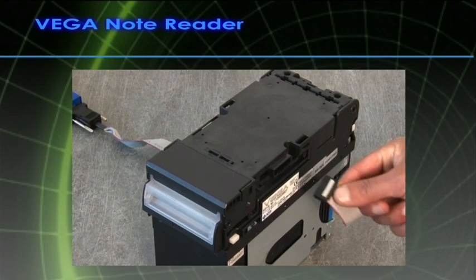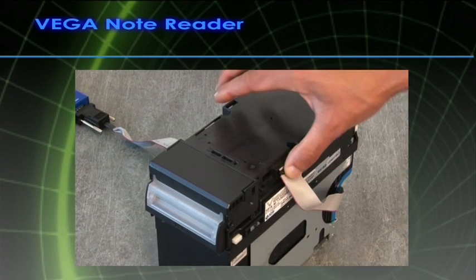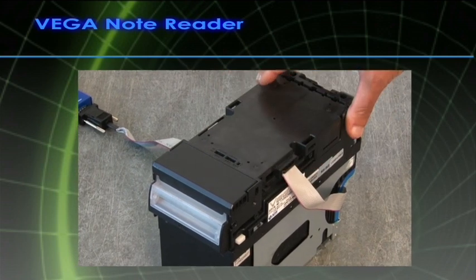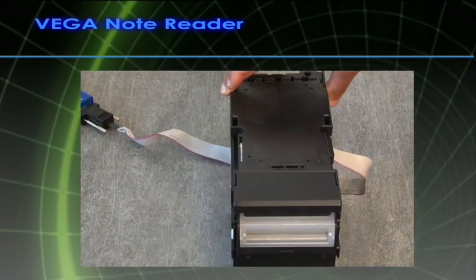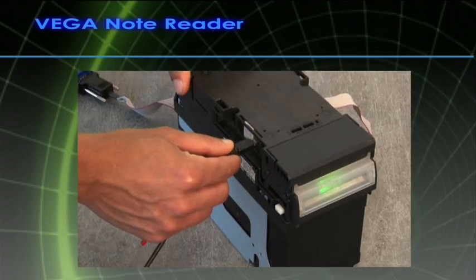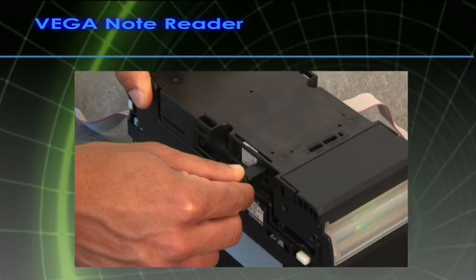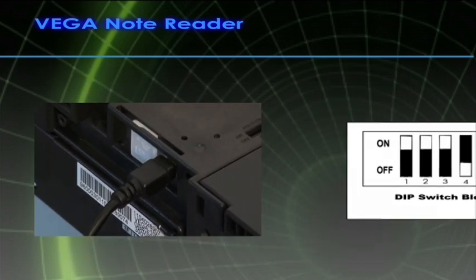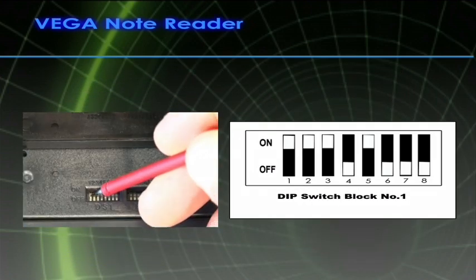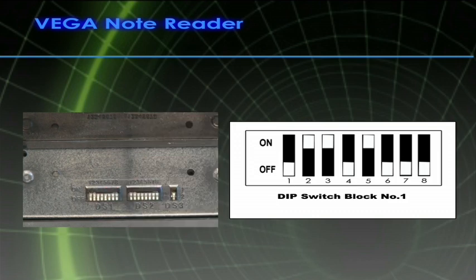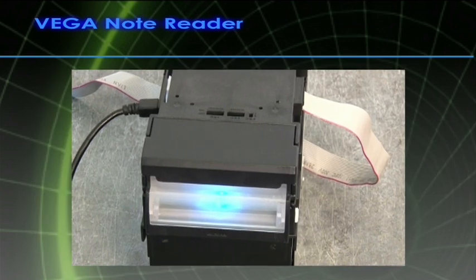Turn the power on. Then the front panel LED will slowly blink in green. Connect the USB cable to the Vega unit. The other end of the cable should be connected to the USB port of the computer. Set dip switch block number 1, switch number 1 off. The front panel LED will begin to blink in a cyan, white and blue color sequence.